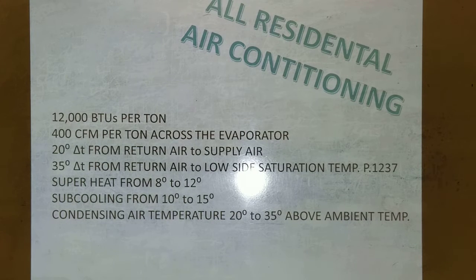We'll get into that. Superheat is going to run from 8 to 12, subcooling from 10 to 15 degrees. The condensing air temperature is 20 to 35 degrees above the ambient temperature. Okay? That make sense? Yes.